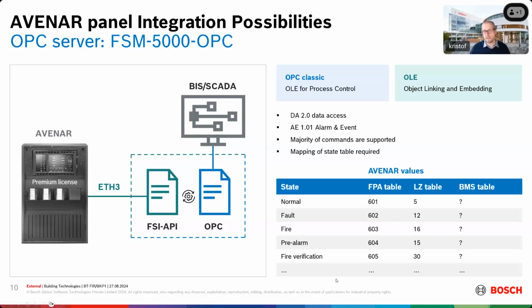We are providing these states on the panel. It is represented in our OPC server as a value. We have two OPC servers, one with the 600 series values or one with the old line status values. Depending on which you installed, in case of a fire, you will have an event 603 created, or an event 16. And this you need to map to the building management system. In OPC, this is not standardized, so this is up to the choice of the building management system.